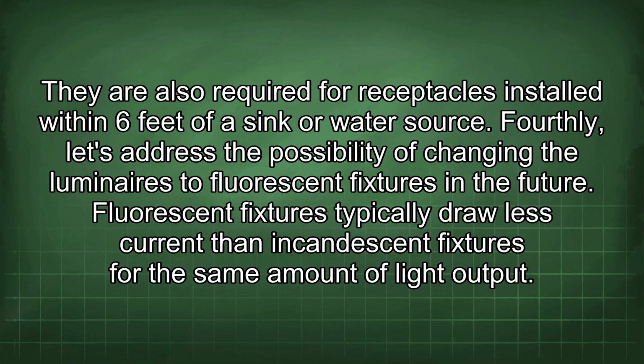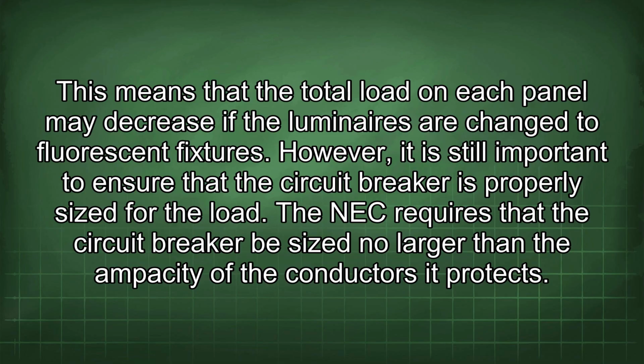Fourthly, let's address the possibility of changing the luminaires to fluorescent fixtures in the future. Fluorescent fixtures typically draw less current than incandescent fixtures for the same amount of light output. This means that the total load on each panel may decrease if the luminaires are changed to fluorescent fixtures. However, it is still important to ensure that the circuit breaker is properly sized for the load.